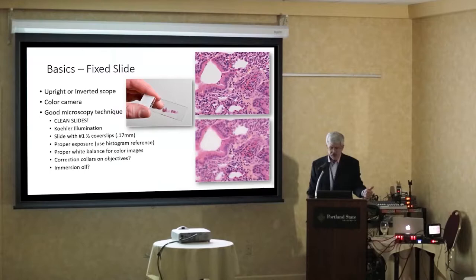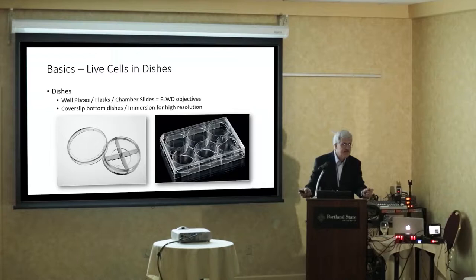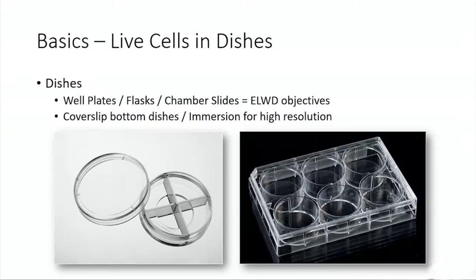Now let's get into live cells. Somebody's coming with live cells — there are different kinds of dishes: a 35 mm dish, a multi-well plate. Generally those have to be looked at on an inverted scope. An inverted scope needs long working distance lenses because the thickness of the plastic underneath is so much that you'd hit it with a regular lens. But if you want high magnification, you can't do it with those — you need to use glass bottom dishes.